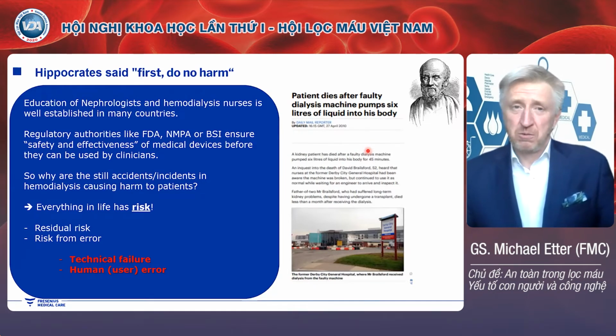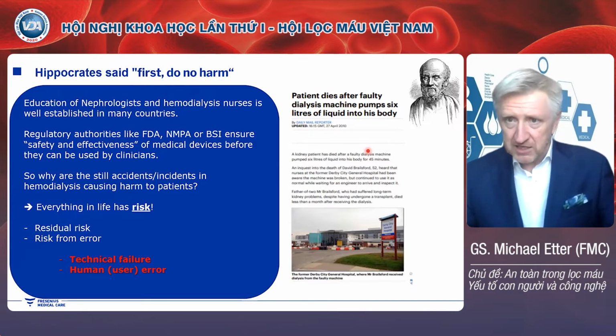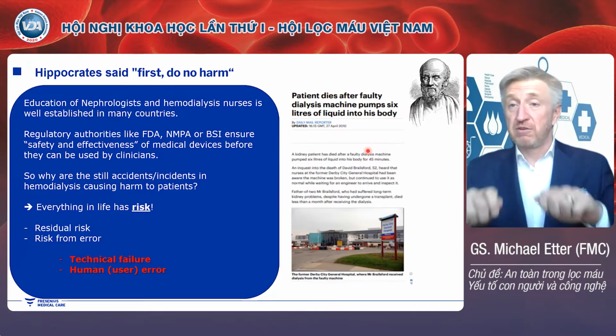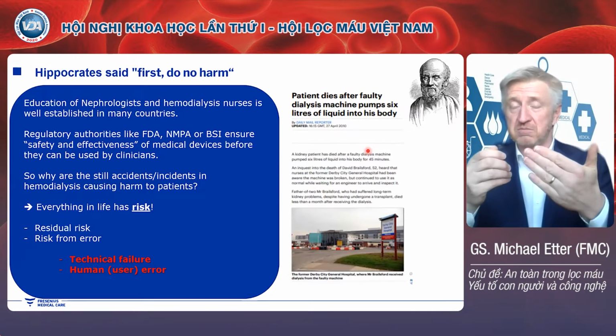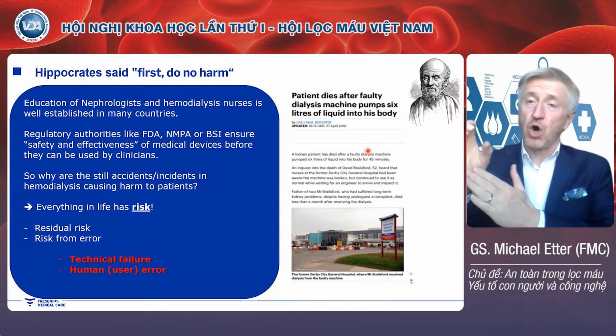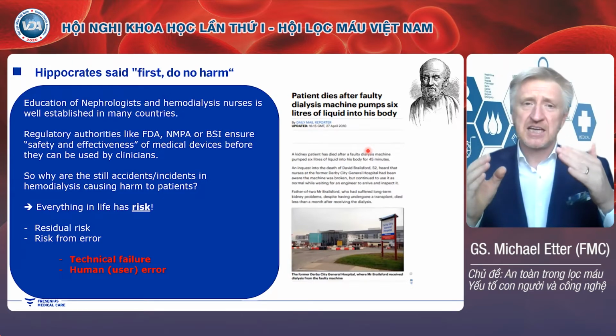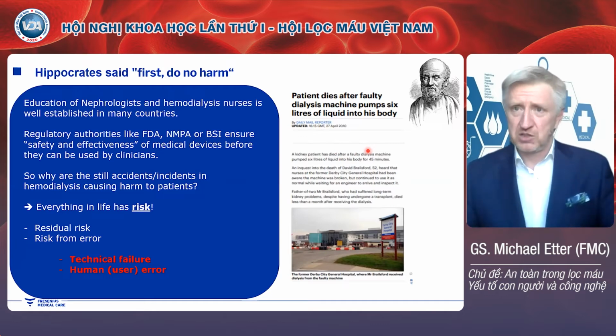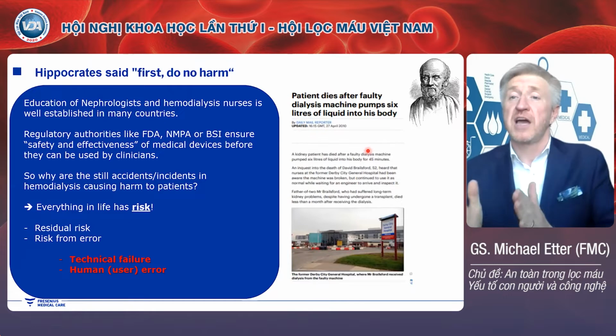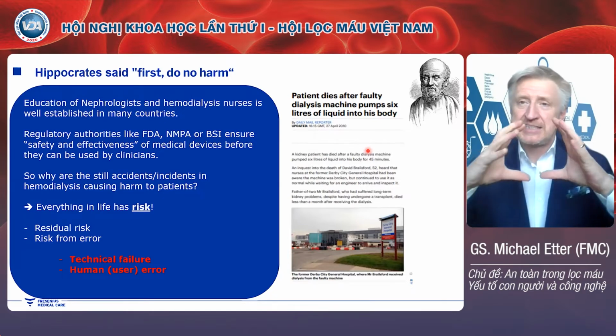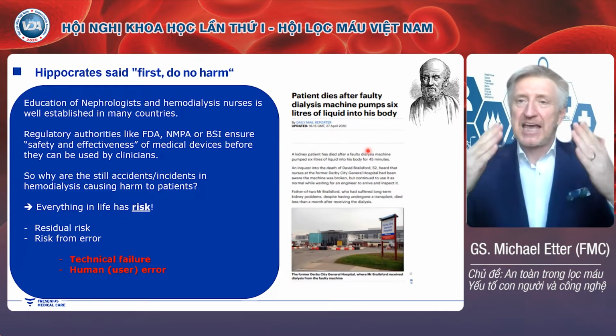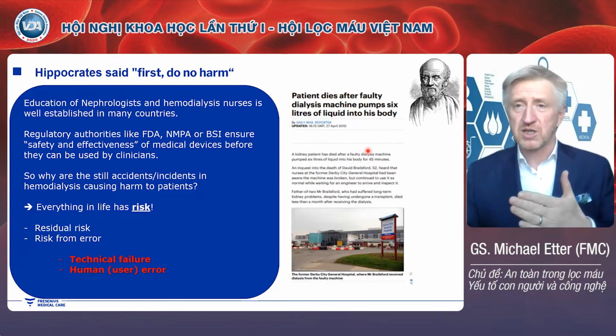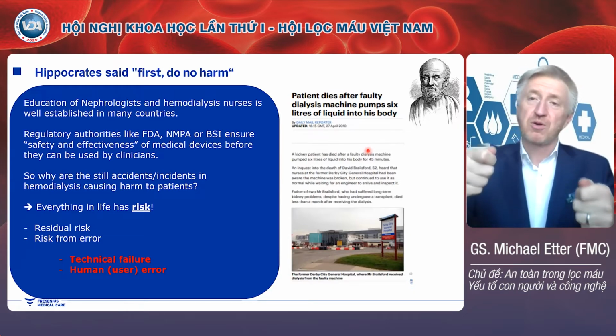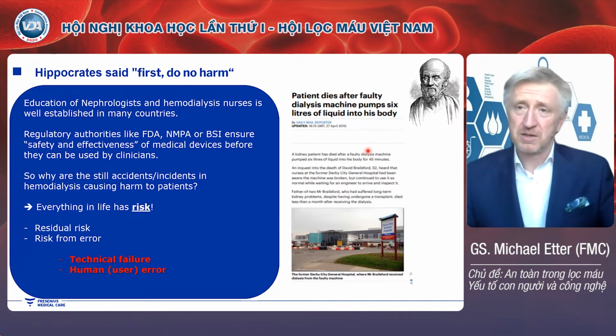So error is something which occurs because either of a technical failure. It could be that you have a faulty part in your dialysis machine. One of the pumps or one of the O-rings is faulty. So that's a technical failure that can lead to a problem. But there is also the so-called human or user error. That means the technology part, the device, actually works as it's supposed to work, but because of incorrect operation, you can create a problem.